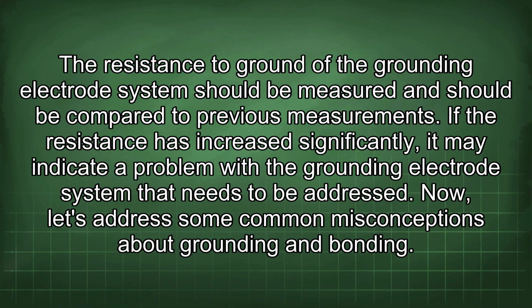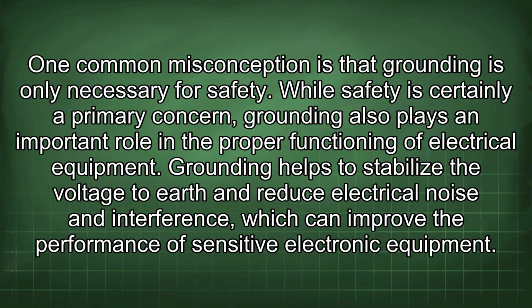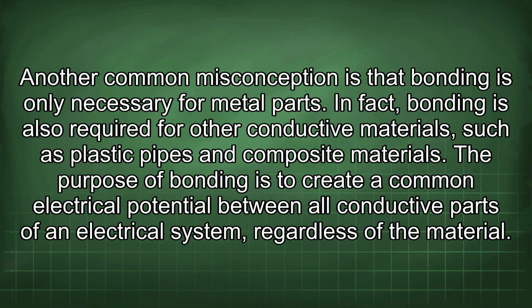Now, let's address some common misconceptions about grounding and bonding. One common misconception is that grounding is only necessary for safety. While safety is certainly a primary concern, grounding also plays an important role in the proper functioning of electrical equipment. Grounding helps to stabilize the voltage to earth and reduce electrical noise and interference, which can improve the performance of sensitive electronic equipment.